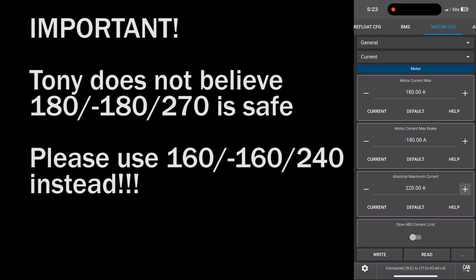Now we need to go to motor config up at the top, and then in general there's current. In currents we have 180 and minus 180, and the abs max is only 220. VESC Tool itself tells you right away what the problem is. I don't know why Tony was ignoring that, because you can read it yourself, pause it, read it, but Tony should have read it too. You need 50% higher abs max than your current max, and for some reason Tony doesn't seem to understand this. I've had discussions with him about it. But if he's worried about anything, he should be worried about the 180, not the 220. Let's keep it simple. Set it to 270.